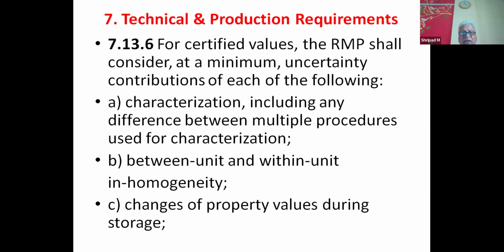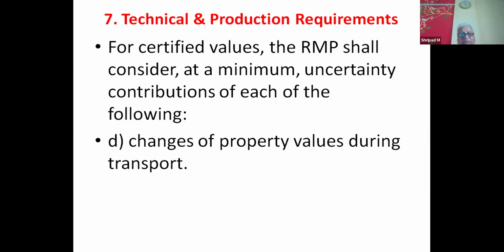So these are the requirements. For certified values, what are the minimum uncertainty contributions? That is characterization. Then between-unit and within-unit homogeneity, that is your homogeneity, and changes in the property value during storage, that is your stability. These are the main three contributing factors, and changes in the property during transport, that is long term and short term stability. So these are the main contributors for consideration as uncertainty contribution.